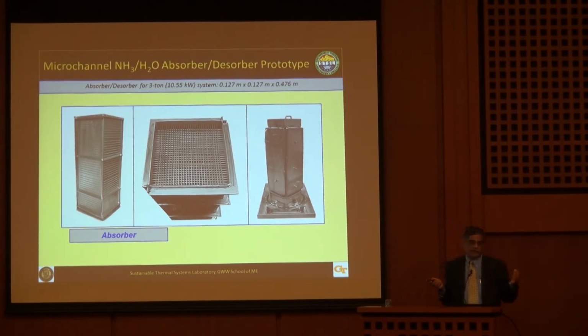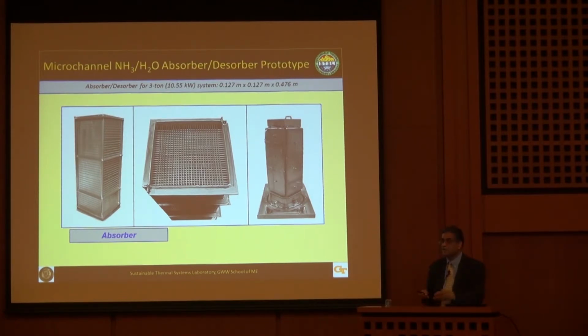Since these are microchannels, the tube-side heat transfer coefficient is very, very high. Because of this lattice structure and the frequent interactions of droplets as they fall, the outside heat and mass transfer coefficients are also very high. These are self-distributing, so even if it's maldistributed at the top, it redistributes itself, letting us achieve a very compact geometry.